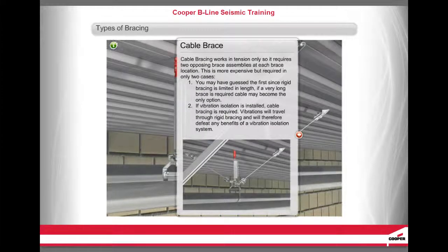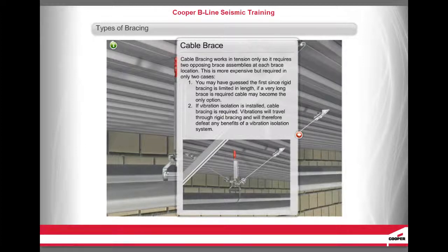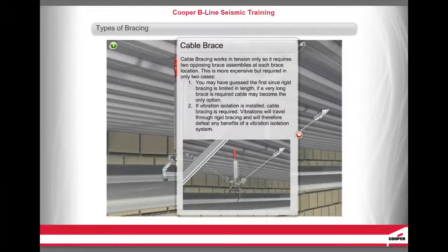Cable bracing works in tension only, so it requires two opposing brace assemblies at each brace location. This is more expensive but required in only two cases: first, if a very long brace is required, cable may become the only option; second, if vibration isolation is installed, cable bracing is required, because vibrations will travel through rigid bracing and defeat any benefits of a vibration isolation system.